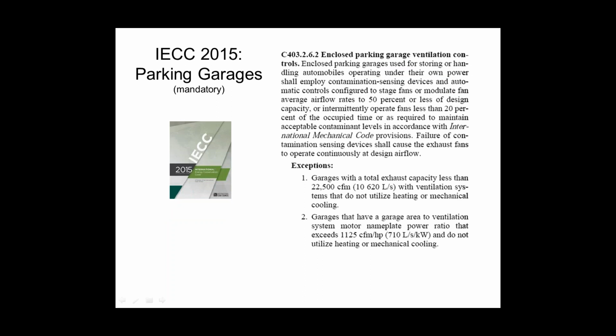There are other demand ventilation systems that are now required by code as well, specifically ones for parking garages. Obviously, we wouldn't use CO2 sensors in this case. We would use carbon monoxide sensors for cars and nitrogen dioxide sensors for diesel vehicles, or some combination of those if I had a multi-use space. So in those cases, we have to have the ability to stage down or modulate fan airflow.